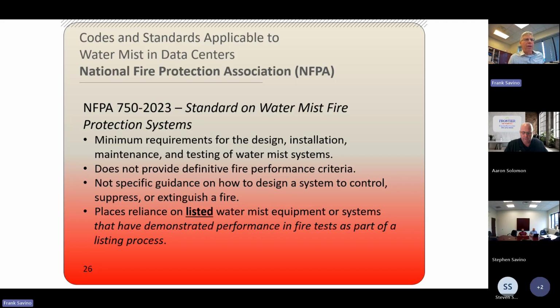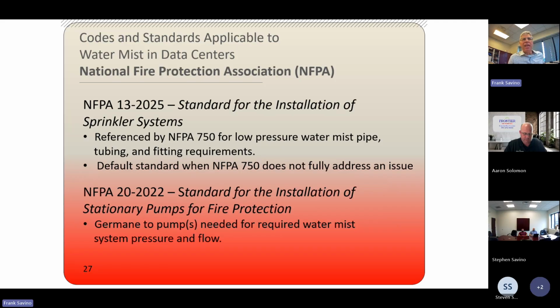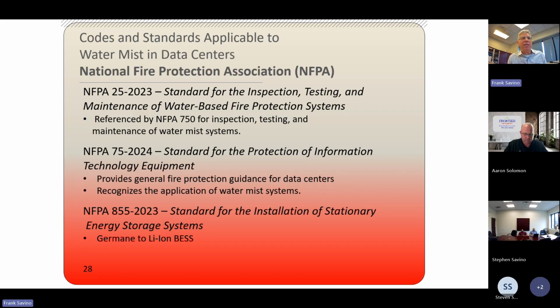we talked about earlier. NFPA 13, the standard for sprinkler systems, is referenced by NFPA 750. And it's really kind of like the default standard. If 750 doesn't address something, the default is you go back to 13 and say, hey, what does 13 say about that? NFPA 20 is a standard for fire pumps that applies to water mist systems. All the rules that govern fire pumps are there. NFPA 25 is a standard for inspection, test, and maintenance of water-based systems. That also applies to water mist systems.